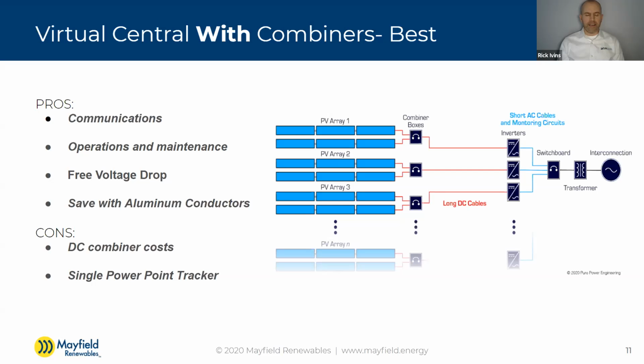Yeah, as the conductor sizes go up, the difference in price between copper and aluminum spreads. So as you start going from a number 10 to several sizes more, to 2 to 250 all the way up to 500, that delta in pricing increases almost exponentially in what it takes to replace copper with aluminum. So when you have the opportunity to use aluminum, we really try to push for that. Most of the time it is accepted by our clients and they're okay with it. Some have some initial pushback, but once they see the price difference, or they send it to their contractor and say, "Give me the two prices," and they see the price of aluminum, they're like, "Oh, that's too good to pass up." So risk reward, and like we said, the risk isn't really there; it's more perceived risk.